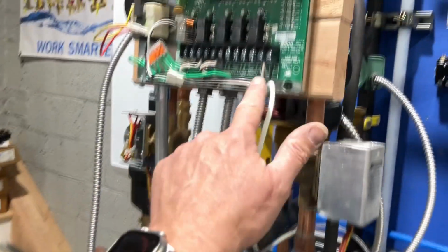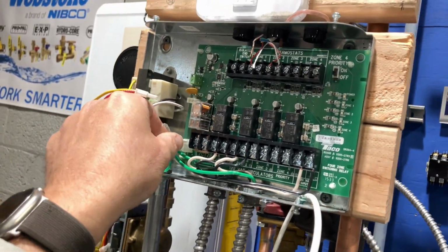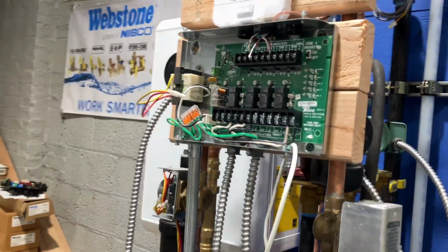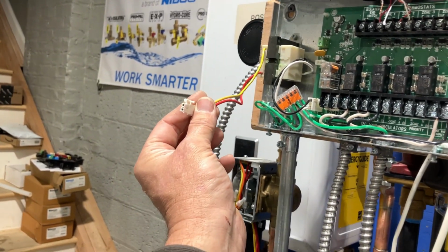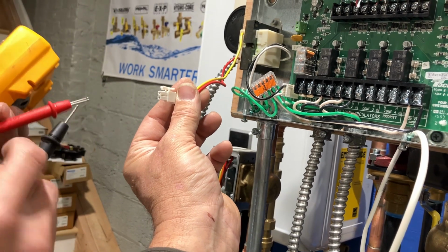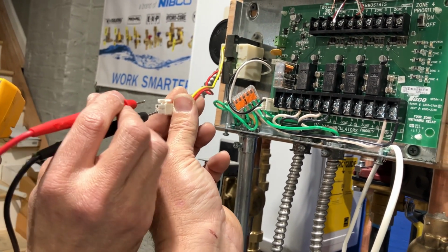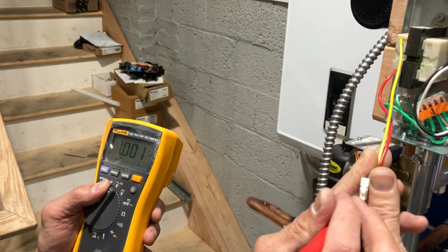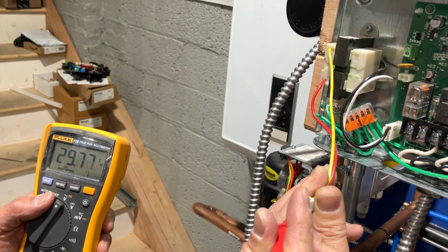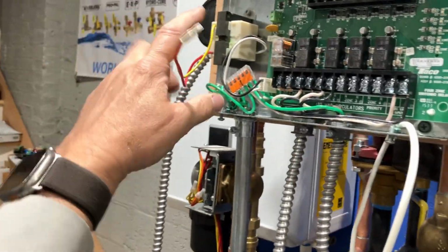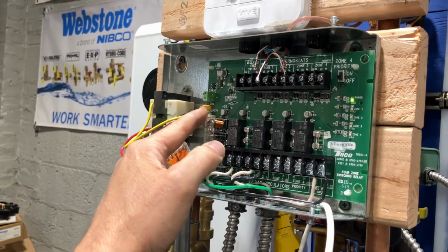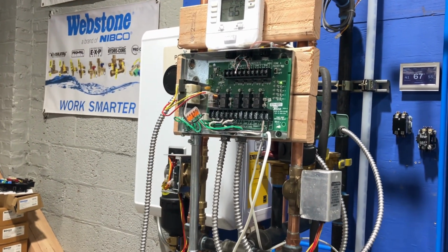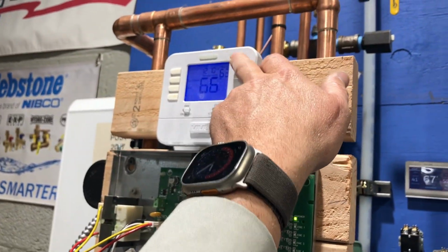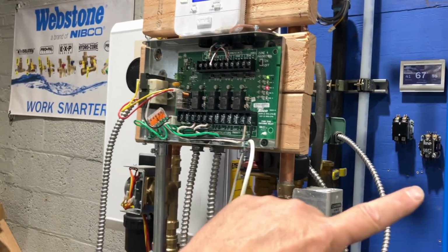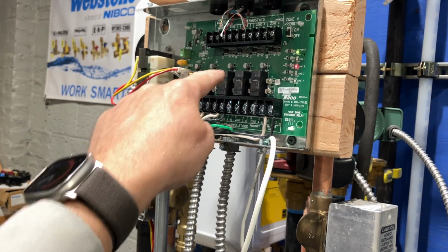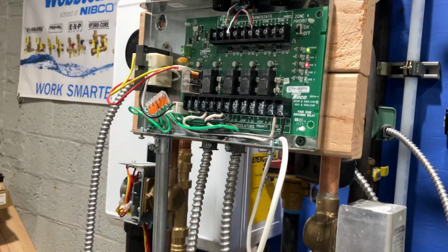Okay? So we have power here. Now, if I plug in that transformer, okay, I should have 24 volts here. Let's check for 24 volts. You got 29 volts. You got voltage there, right? So you know the transformer is good. Okay. So let's plug in our transformer. And look, our light has reappeared. Right. Okay. Now, let's turn on our zone. Our click is the circulator relay energizing zone 2. Let's get our voltmeter. Let's measure voltage between N and H on zone 2.